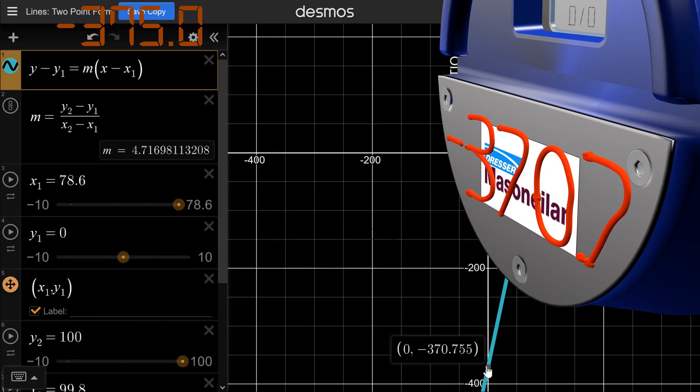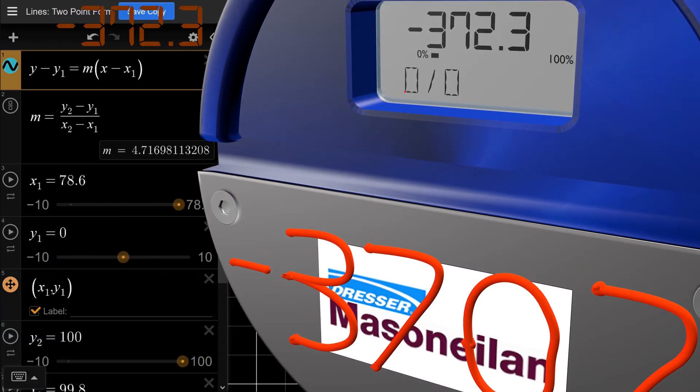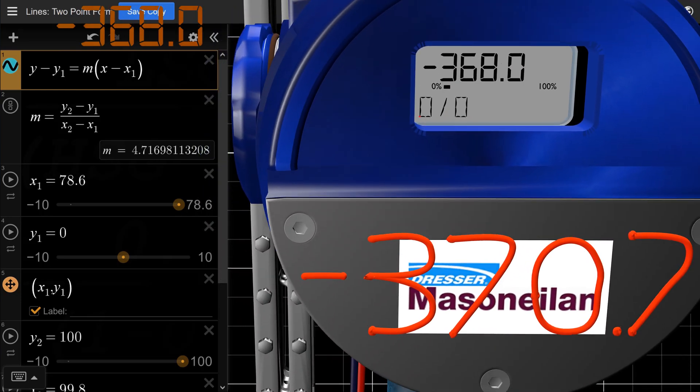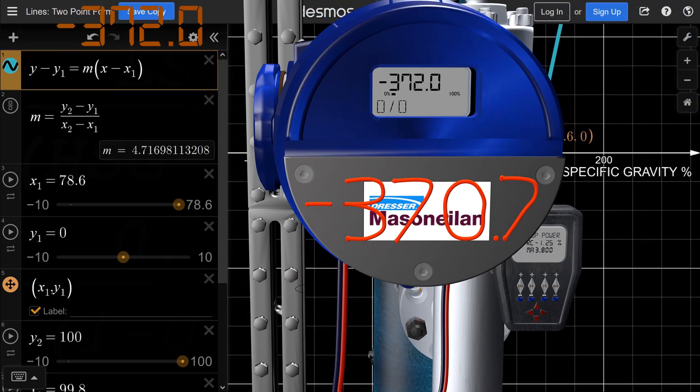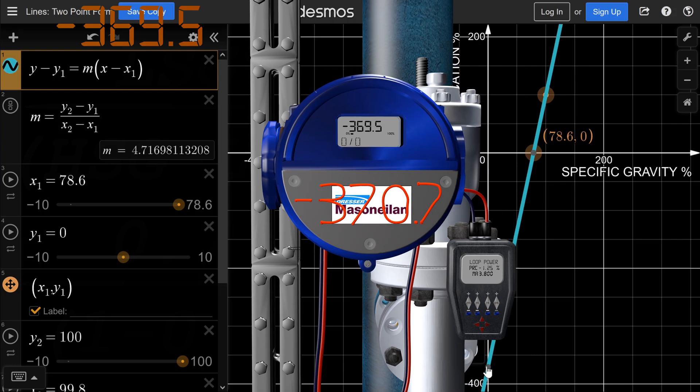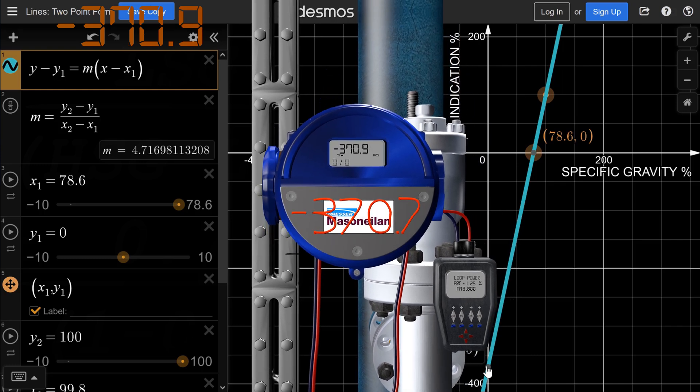Now we write confidently this value on the front cover. For the following years, we will be able to check the transmitter in both 0 and span, just closing the block valves and emptying the chamber. This is the ultimate check which could be done easily from the unit operators.